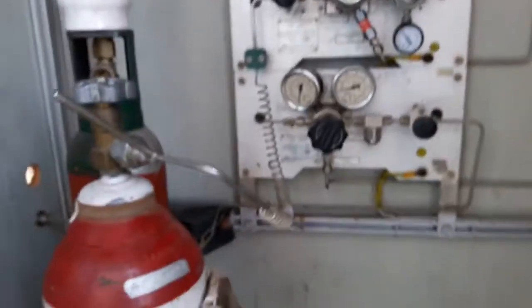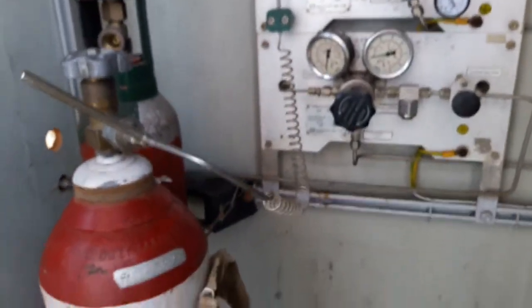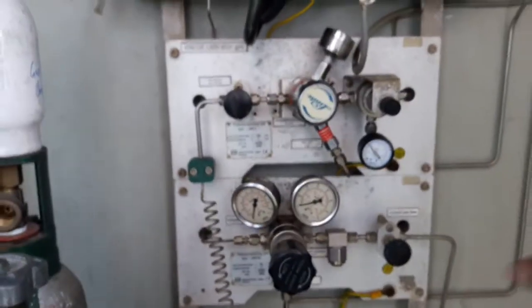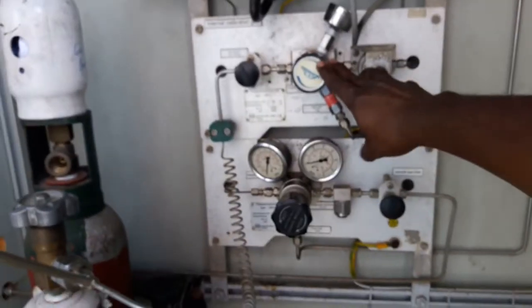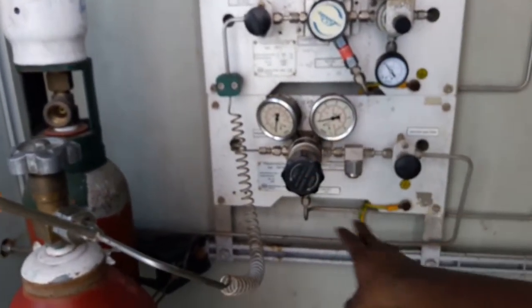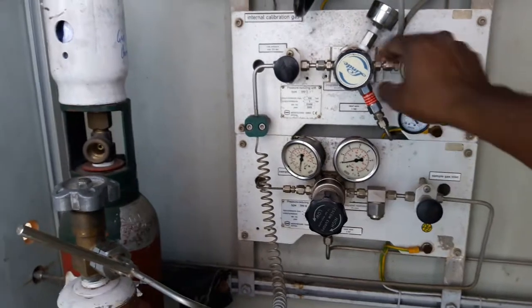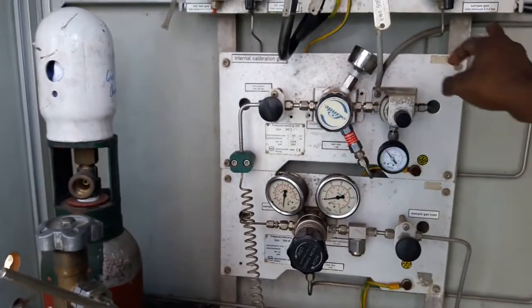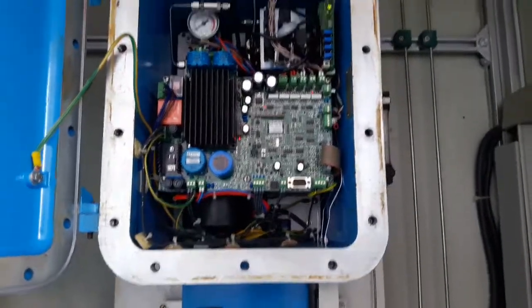And we have connected this calibration gas cylinder. The top regulator is for calibration gas and the bottom regulator is for sample gas inlet. We have to set the calibration and sample gas inlet to 0.5 to 3 bar. It should not be more than 3 bar.